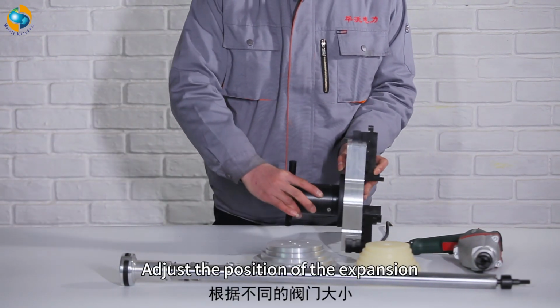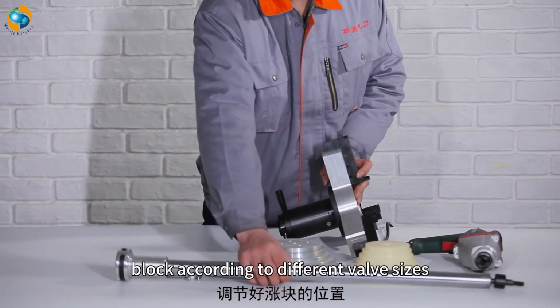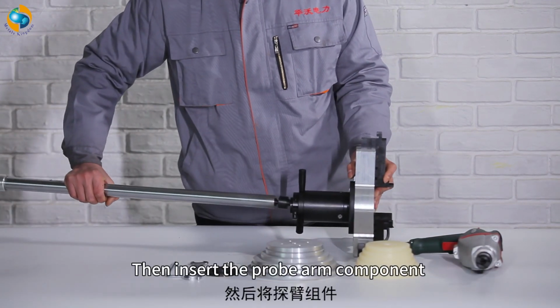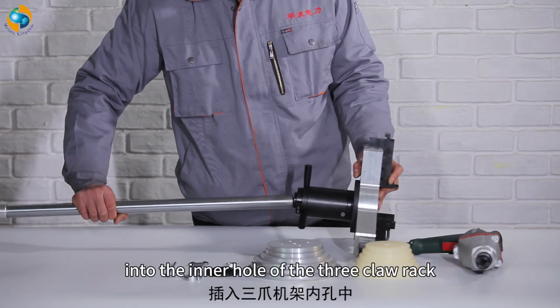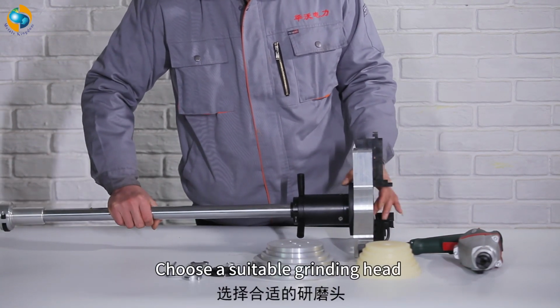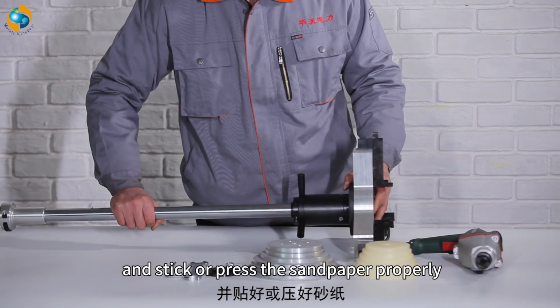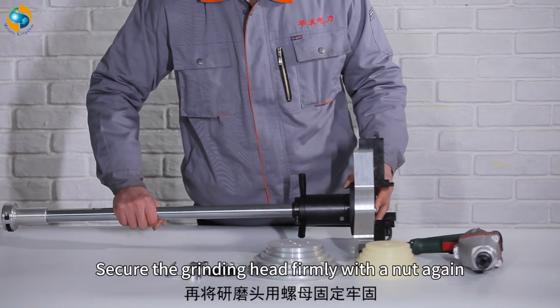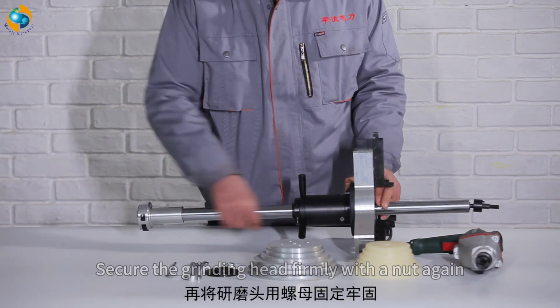Adjust the position of the expansion block according to different valve sizes. Then insert the probe arm component into the inner hole of the 3-claw rack. Choose a suitable grinding head and stick or press the sandpaper properly. Secure the grinding head firmly with a nut again.